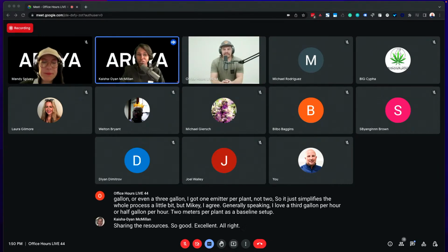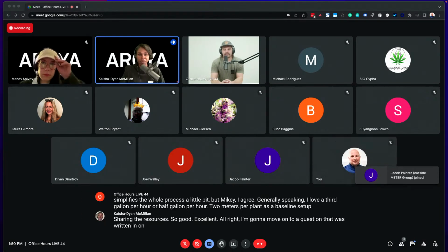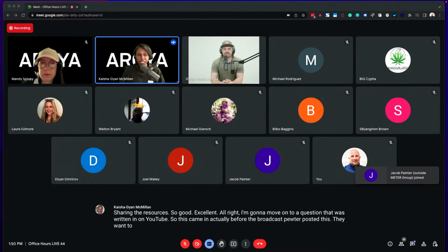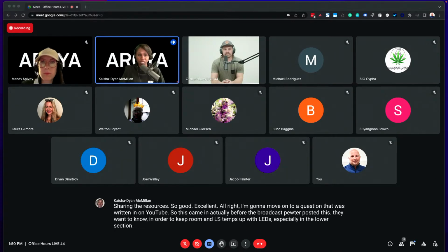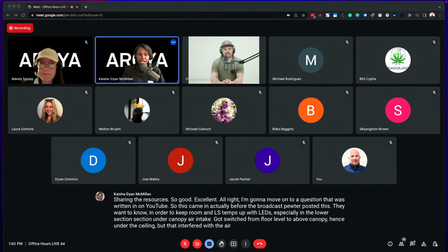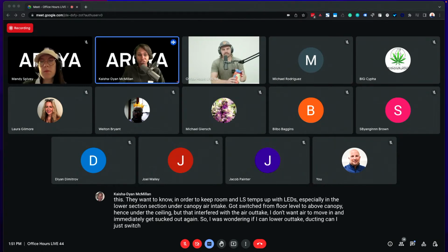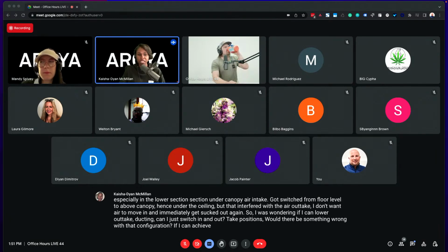Excellent. All right. I'm going to move on to a question that was written in on YouTube. This came in actually before the broadcast. Peter posted this. They want to know, in order to keep room and LS temps up with LEDs, especially in the lower section under canopy, air intake got switched from floor level to above canopy, hence under the ceiling, but that interfered with the air outtake. I don't want air to move in and immediately get sucked out again. So I was wondering if I can lower outtake ducting. Can I just switch in and outtake positions? Would there be something wrong with that configuration if I can achieve the right temps with less cooling and heating? Thanks. Does that make sense to you, Seth?